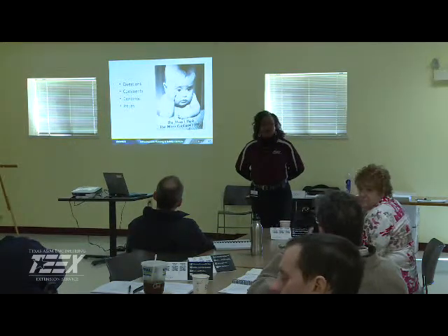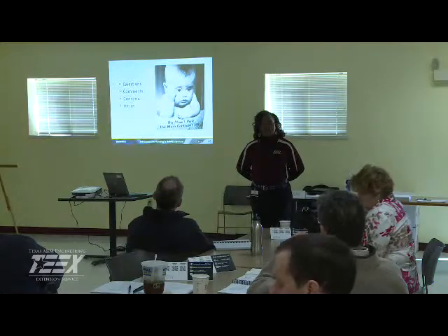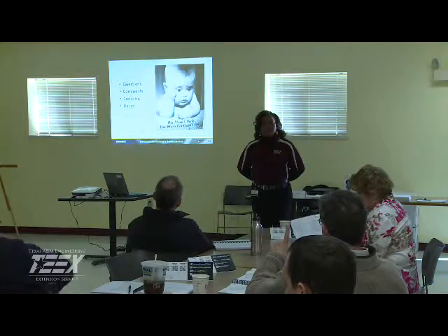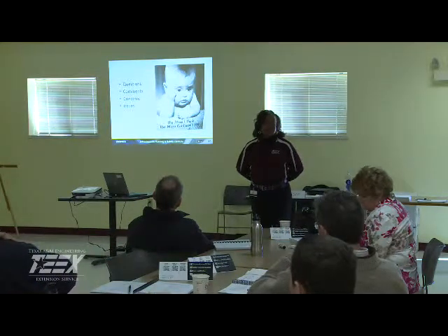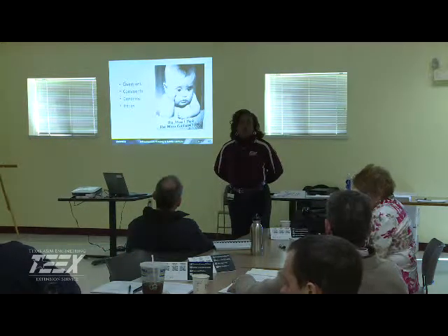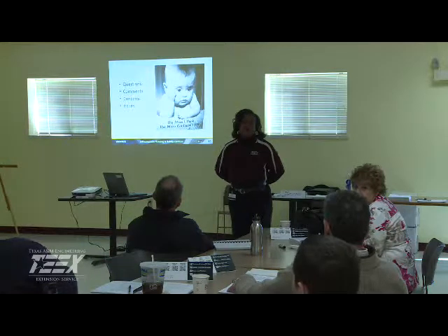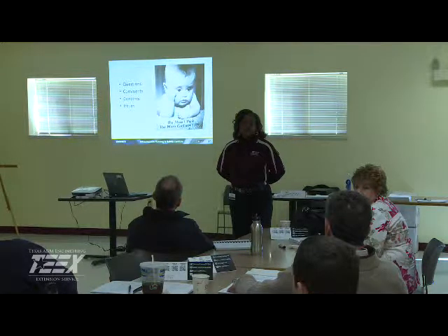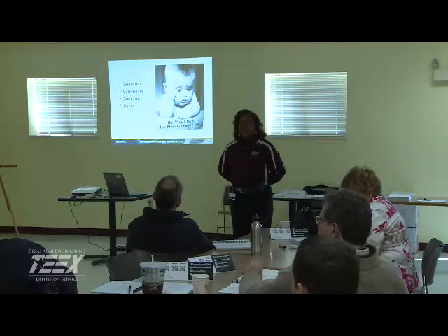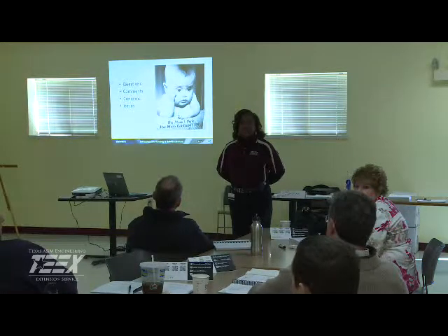Yes, sir. The action level, I can't remember if you mentioned that earlier, was that the 90th percentile of all the samples is still the action level now? Yes, yes. So in other words, you get 10 samples, 9 of them have to be below the action level. That's right. 0.015 for lead and 1.3 for copper. If 10 is 0.015, and 9 is 0.010, then you're okay. Yes, that's exactly what that means. Good question. It's not just one sample, it's all. You're looking at that 90th percentile.